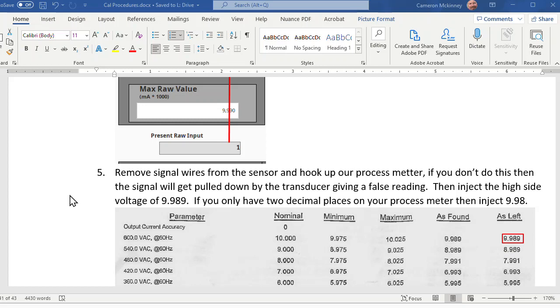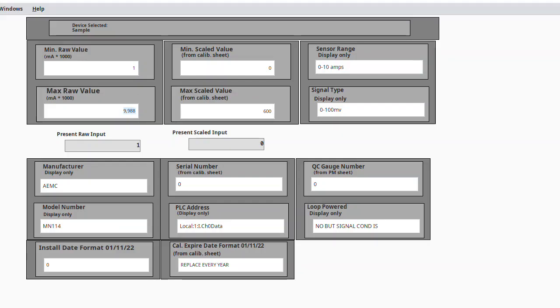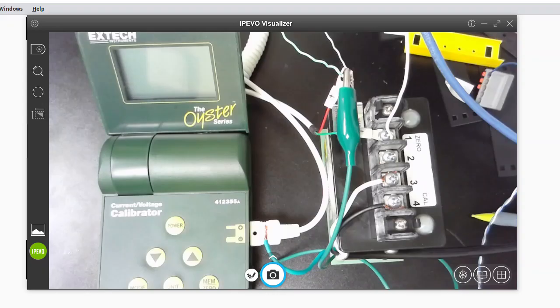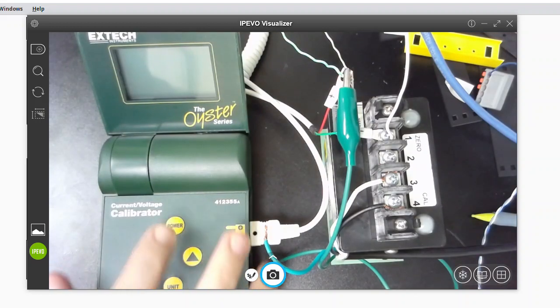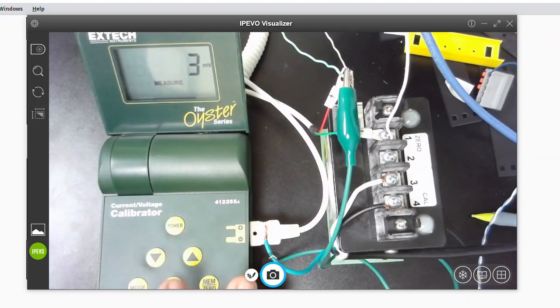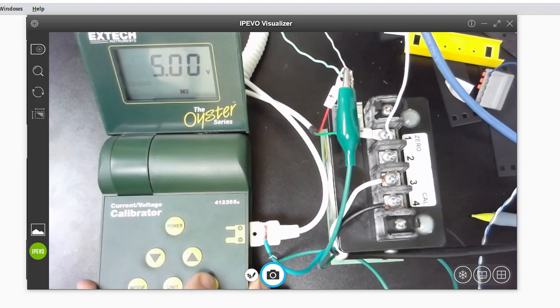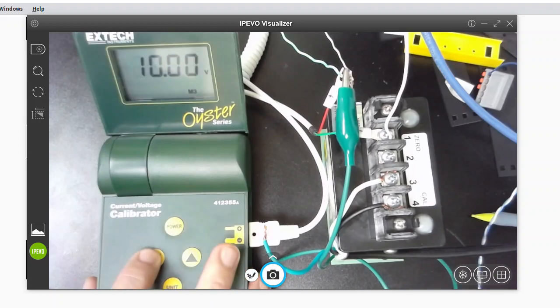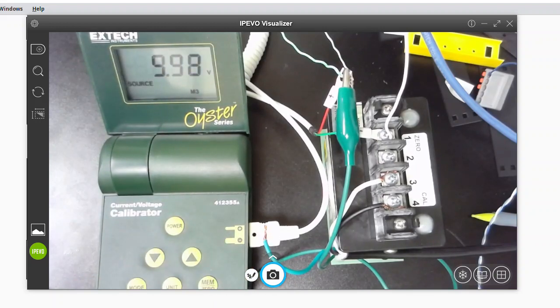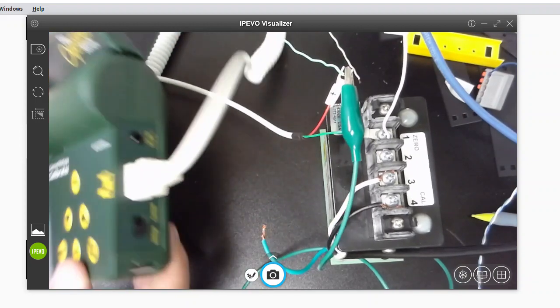So we're going to inject a high side of 9.98 on my little clamshell transducer as soon as I get that up. There we go. Power button. We're going to hit the mode to source. I don't want to scroll through everything with the up and down, so I'm just going to hit the memory button, get myself to 10 volts, and then back it down. That's a little bit easier. So now I'm simulating 9.98 volts. When you use this process meter, make sure that you have this voltage selector switch set correctly.